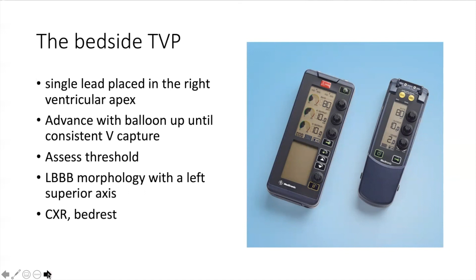For each patient with the TVP, it's well advised to check daily to make sure it's functioning okay. To do this, you need to check the threshold capture output every day. On the box, you increase the heart rate via knob 1 such that all beats are paced. Next, you decrease the output on knob 2 until pacing ceases and the native rhythm is seen. This is the threshold of the temporary pacemaker. As soon as you see this though, increase the output back to its initial value. Generally we do this at 5 to 10 times the threshold, usually 10 or 15 milliamps, and then turn the rate back to its initial value.